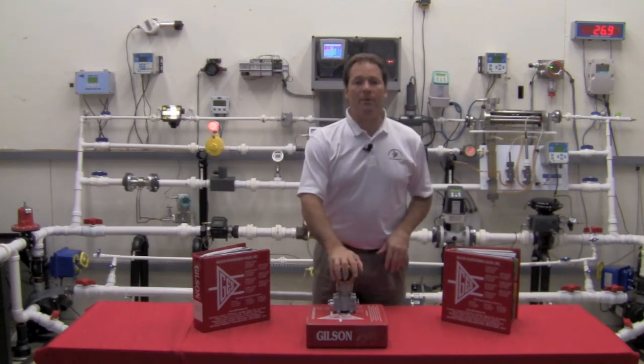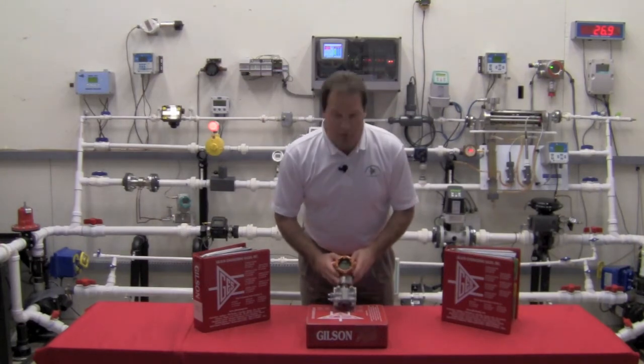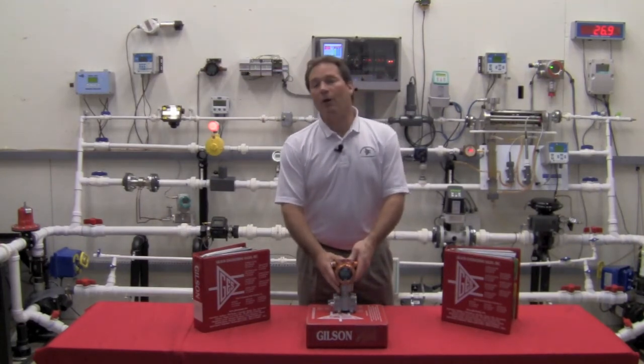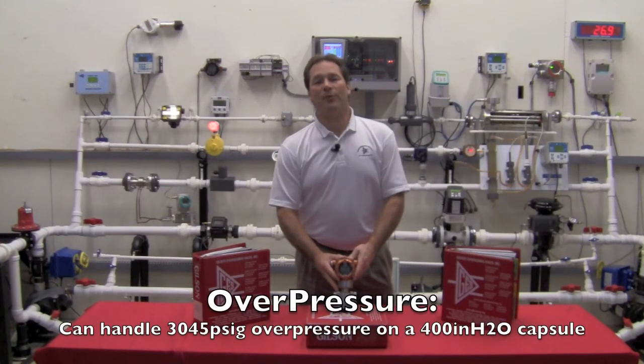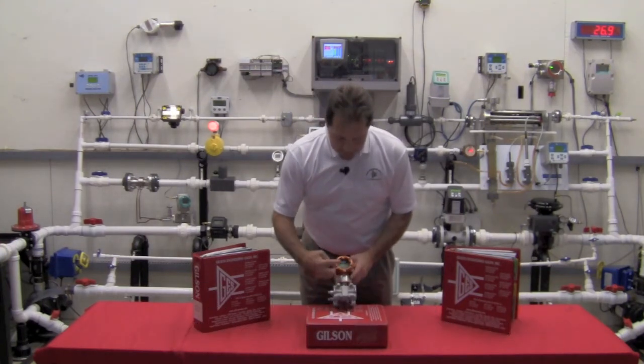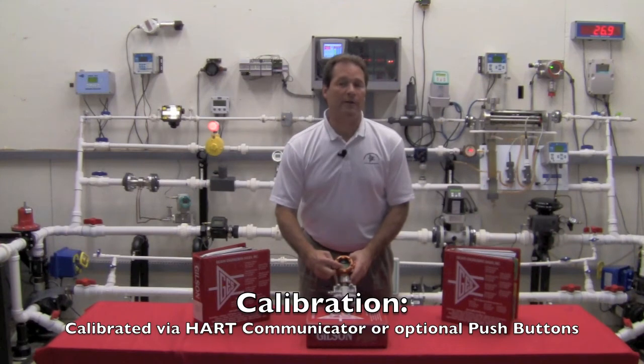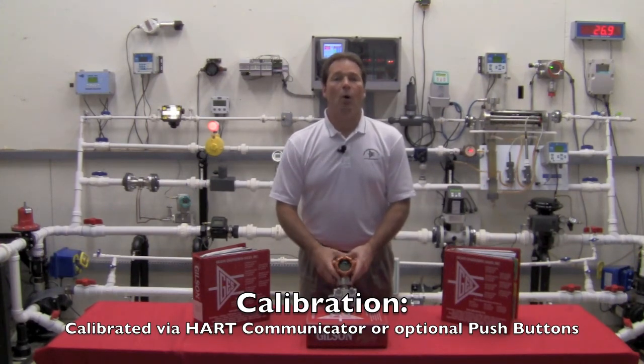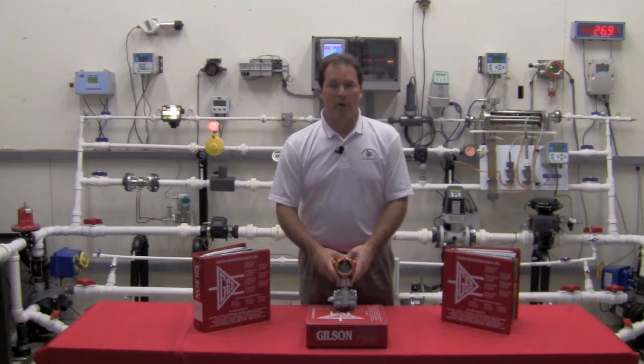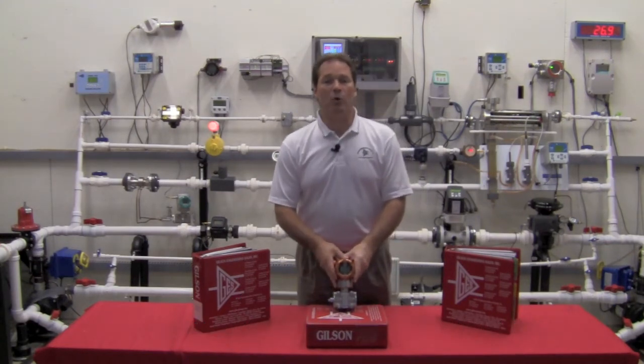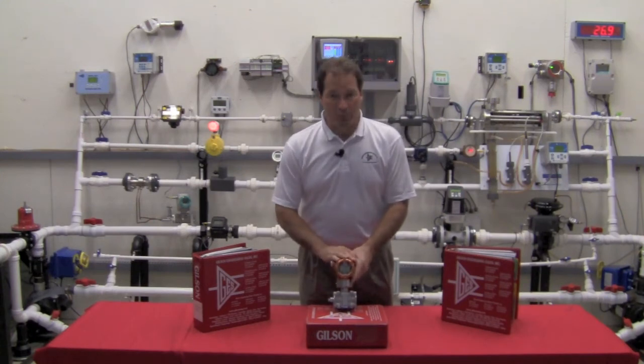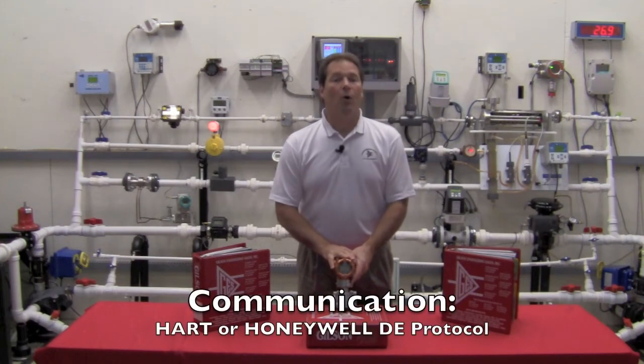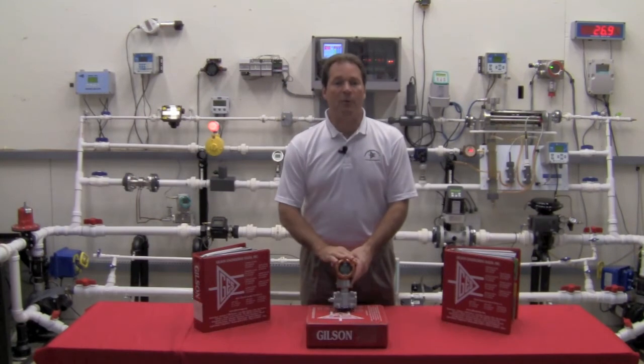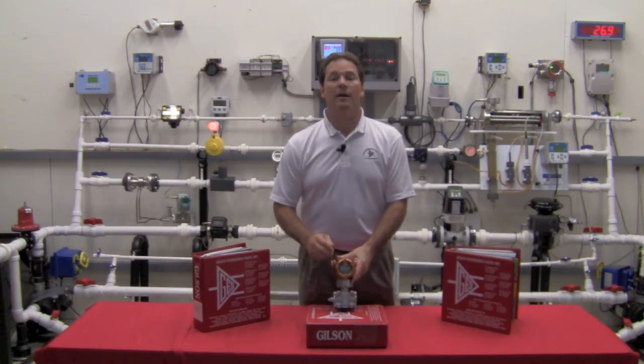We have overpressure capability unmatched in this transmitter. This particular unit has a measuring range of 2 to 400 inches water column. It's capable of 3,045 psig overpressure. It calibrates either via optional push buttons on the front, which most people don't use or don't order, or via your HART smart communicator. The unit comes standard as a bilingual transmitter, meaning I can speak to this with my handheld communicator either via HART or via Honeywell DE protocol. Same unit, don't order it differently. It comes both ways. It just depends on which communicator you hook up to it, and then it will talk to you.